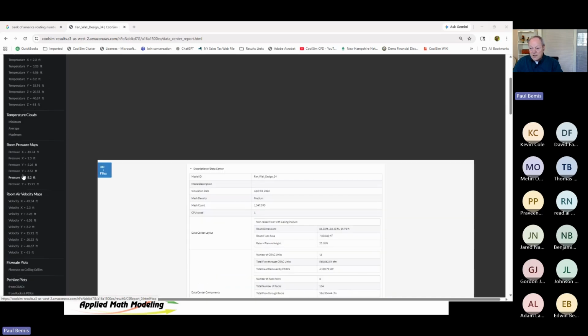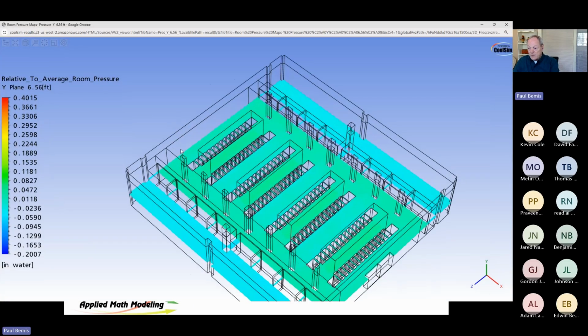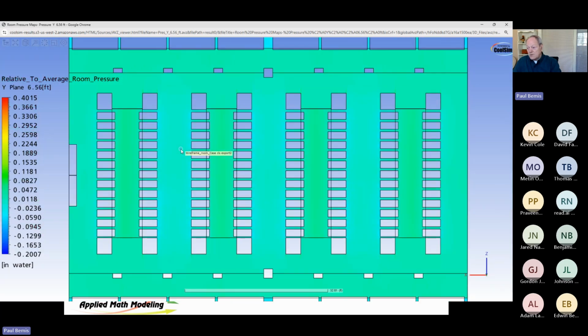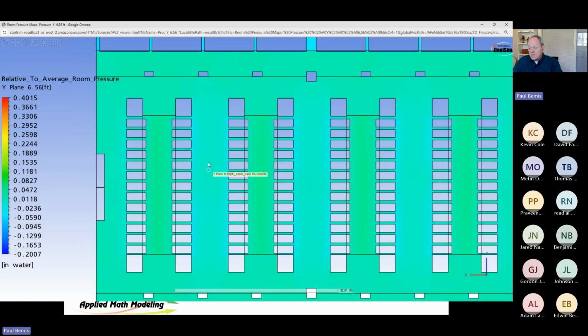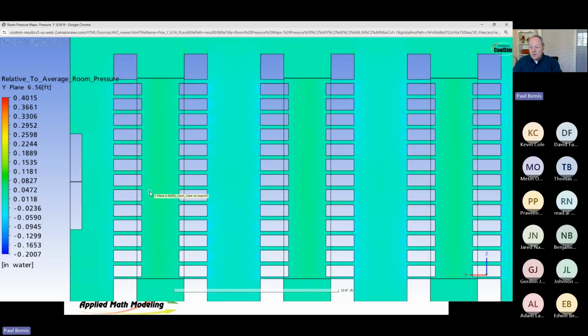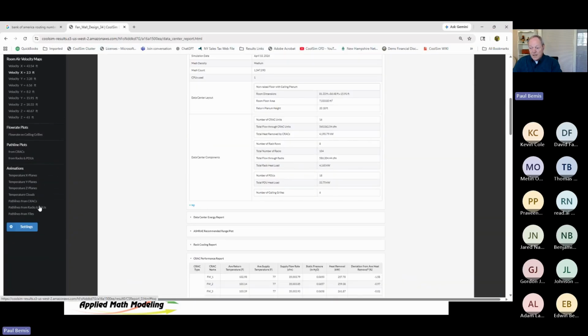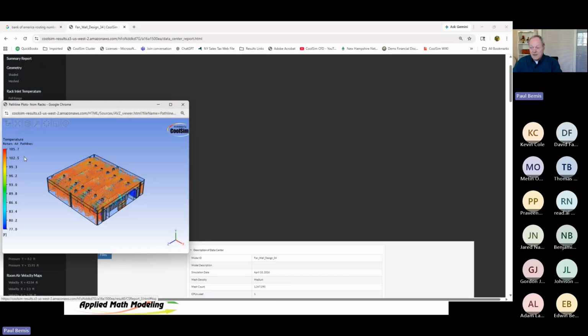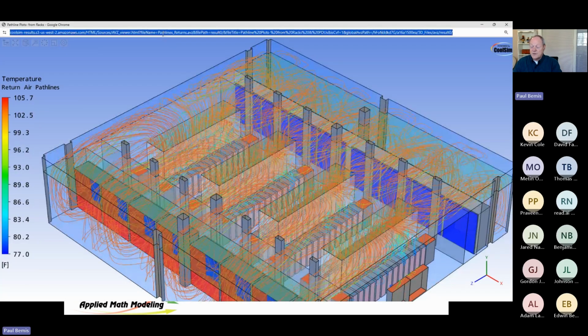And then let's take a look at pressure. This is another interesting one that I was looking at. Take a pressure at the same point. Now, you want the pressure always to be positive in the room compared to what's in the cold aisle. This one doesn't show it perfectly because I don't have the scale set right, but you can see the pressure here is actually lower than the pressure in the hot aisle. The hot aisle is pressurized in certain areas, and that's because you have two high velocity air streams coming at one another. You can see it here in rack path lines. Again, I'll share these.